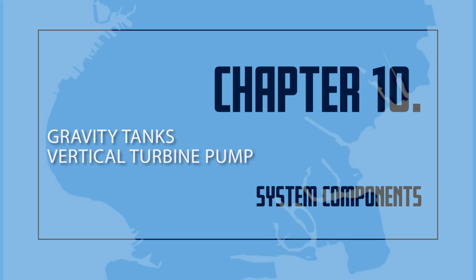The vertical turbine pump. A vertical turbine pump is really a modified centrifugal pump that has the capability to draw water from streams, ponds, and wells. Unlike the standard centrifugal pump, the vertical turbine pump does not need the suction supply to be under pressure for it to operate. Instead, it draws the water into the pump by suction. When it reaches the rotating impellers, the water pressure is increased and then forcefully discharged into the fire protection system.